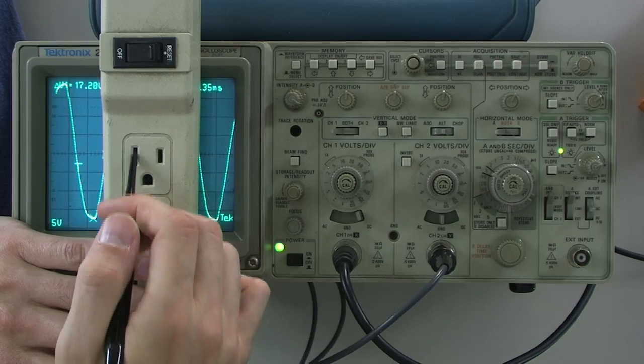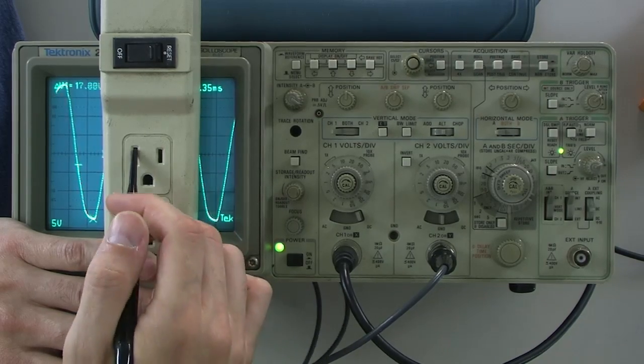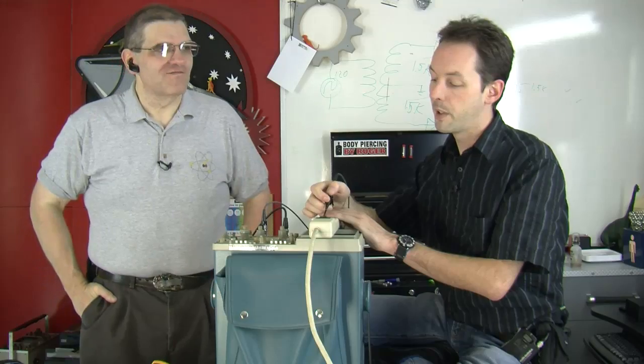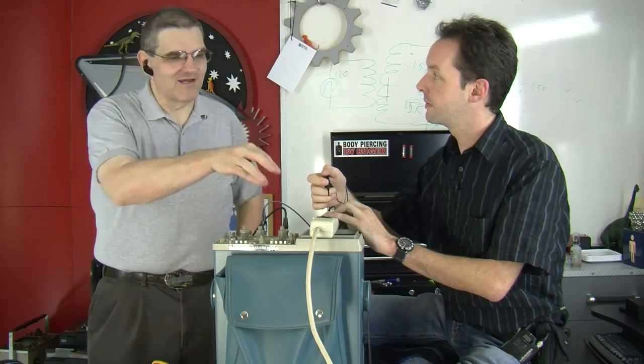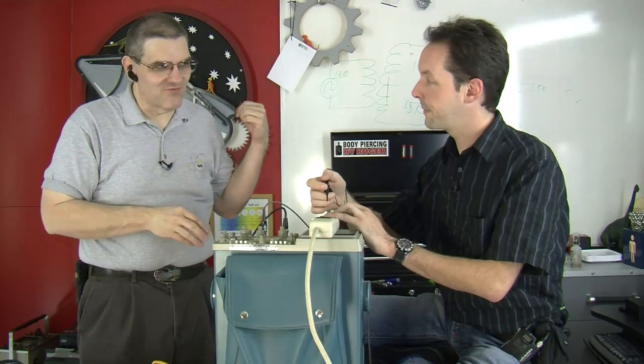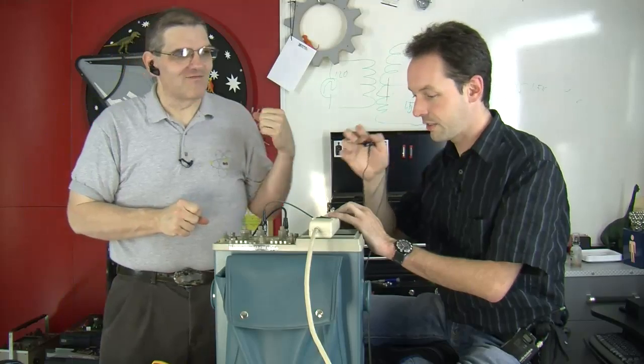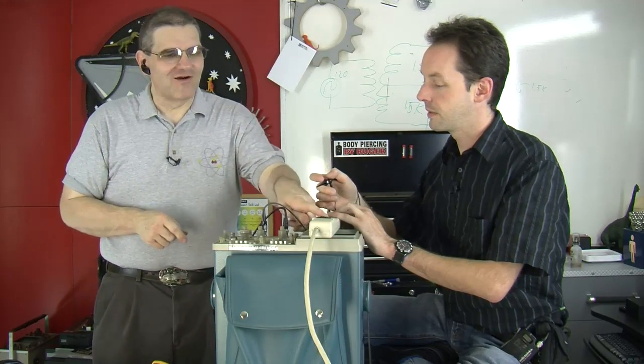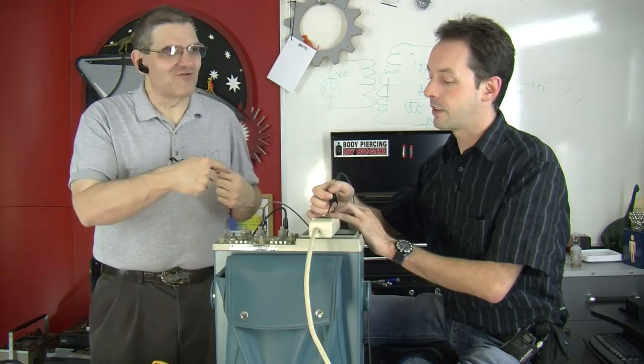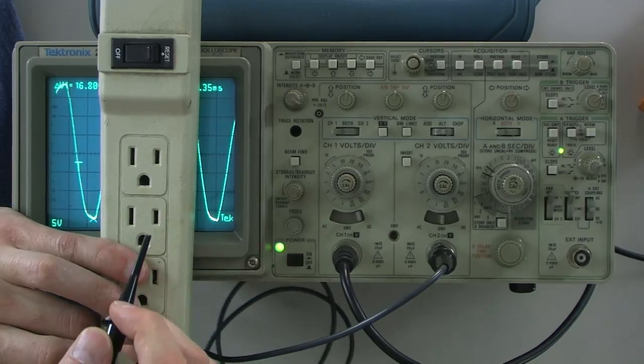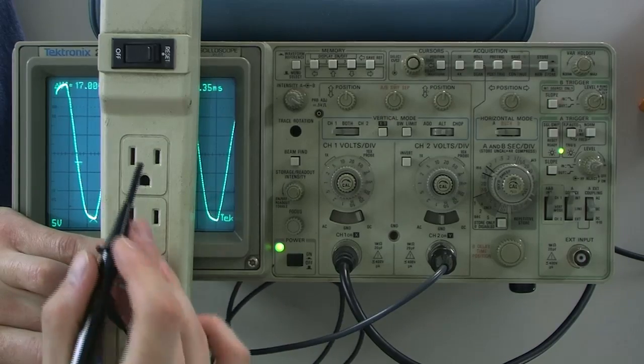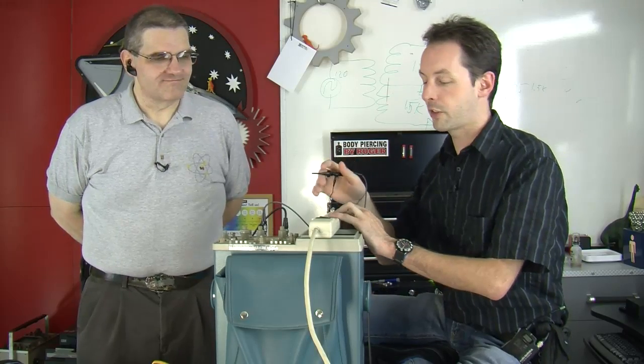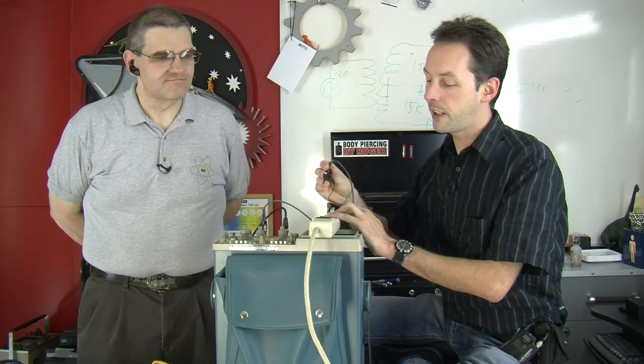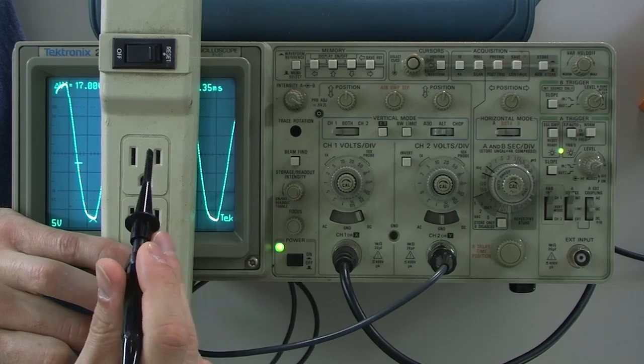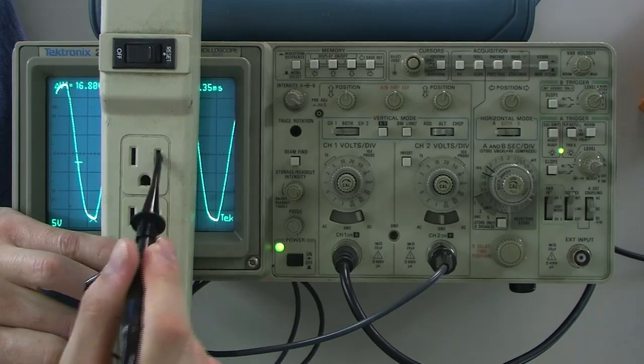And if everything's going really well, between here and here you should ideally have 0 volts, but sometimes neutral will float a bit. If you have a heavy load, you're going to get a voltage drop across your neutral line between your connection point here and the breaker panel. But I don't want to get into that kind of heavy stuff. The grounding conductor is tied to the neutral. This is tied directly at the breaker panel. Yes, that's the fan out point. And we'll do a whole thing on grounded conductors versus grounding conductors. But what I want you to understand is right here you have 110 volts between here and here.